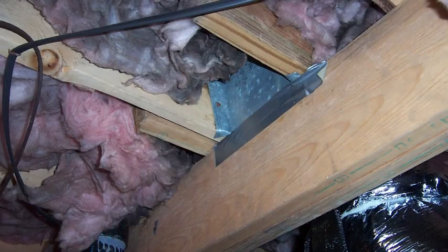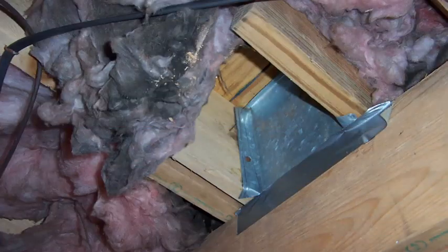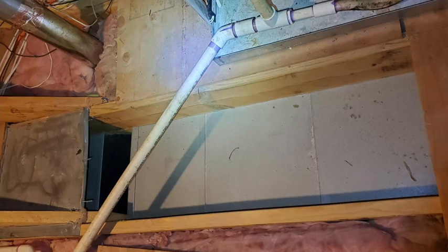I'll use a lot of basement examples, however the basic same issues apply when the layout has the ductwork and equipment in a crawl space, and sometimes it's even reversed and the equipment's up in the attic. There's no question that compared to sealing actual ductwork, sealing panned wall and floor cavities can sometimes be a real challenge to both seal and to price properly. The biggest reason is simply that building cavities inherently leak a lot more than a similar amount of actual ductwork.